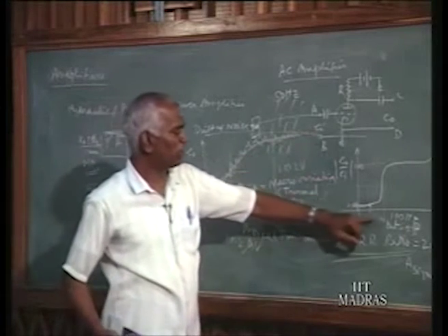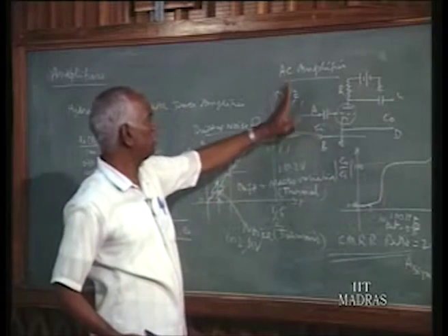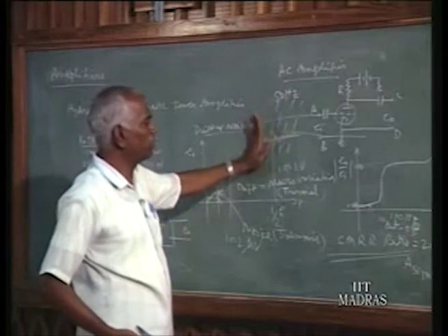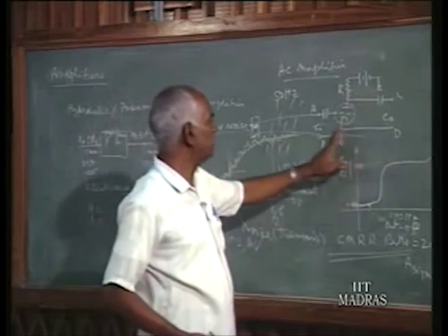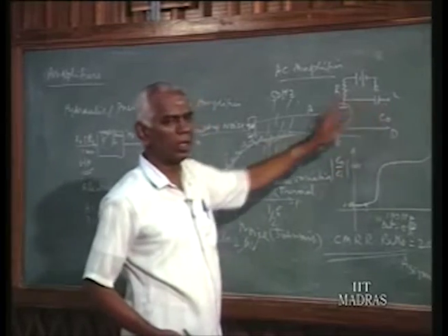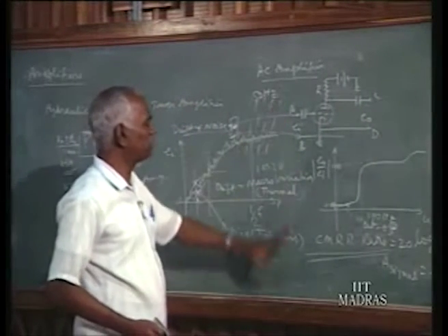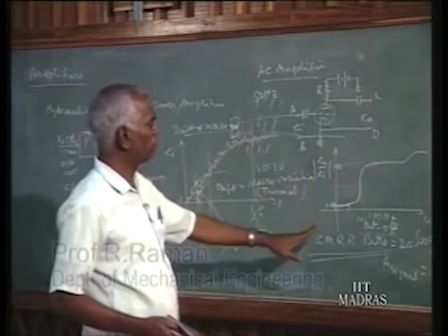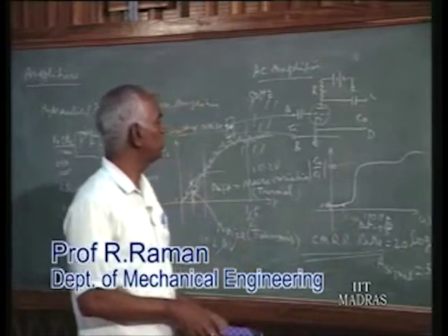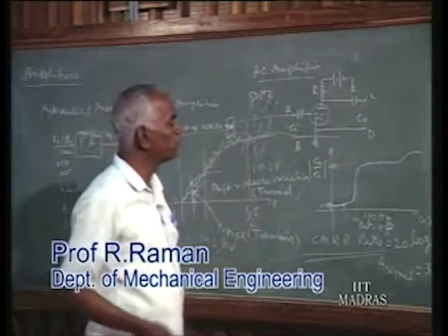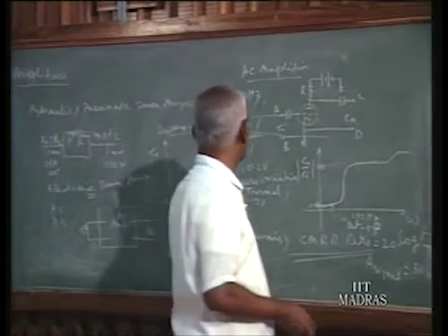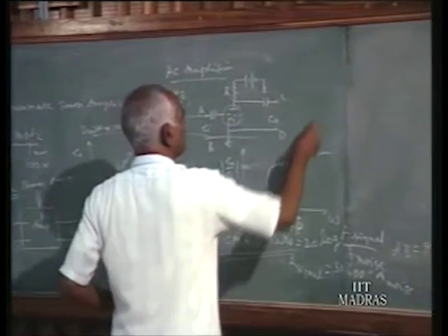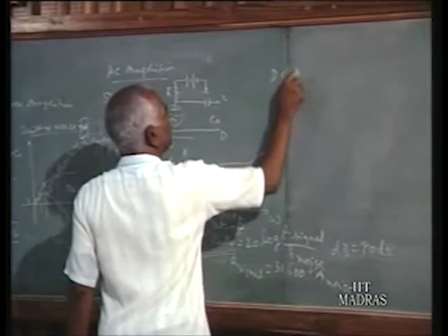This is the advantage of the AC amplifier. That is, it has a higher cutoff frequency, so that any nearby 50 hertz noise can be eliminated automatically by this. And secondly, since only AC can come out, drift will not be there. So the AC amplifier is drift free, and it can filter away the signal of less than the cutoff frequency, especially the domestic power line. Any noise due to the domestic power line can be cut off. That is the AC amplifier. Then the DC amplifier.